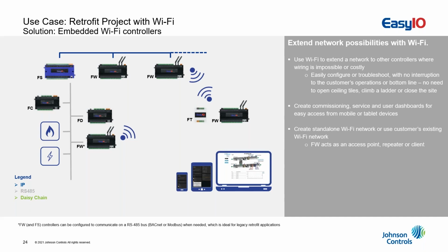We also have used Wi-Fi in vertical markets and retail, and that brought a massive saving for the end user. Because if you have 1,200 shops, and when you want to bring BMS or intelligence to your shop, you have to rewire from the beginning of the shop till the end where the boilers are or where the meters are, and open up the ceiling, and it will cost you 1 day, so you will lose 1,200 days of revenues. That will not help with your ROI, but with Wi-Fi it will, because you can use the existing customer network or create your own network, since we are both an access point or a repeater at the same time. So Wi-Fi for sure will bring you a lot more flexibility.